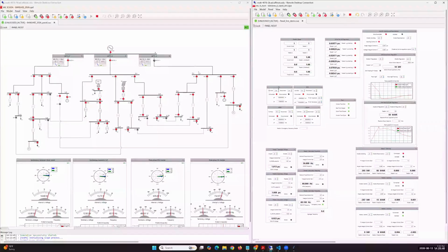So now feeder 3 is running independently islanded with only local secondary frequency control, and we are also still islanding at the POI, and the resources on feeders 1 and 2 are now driving this power to 0. So now we have successfully islanded.